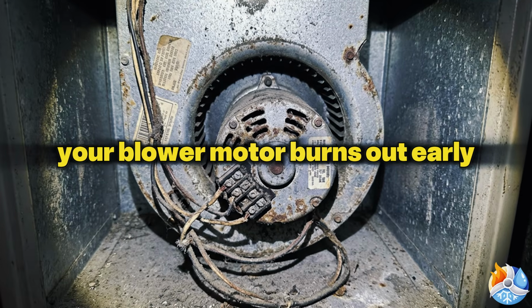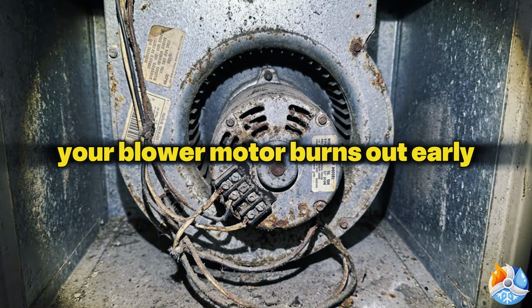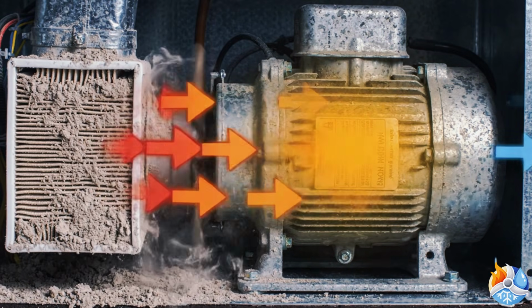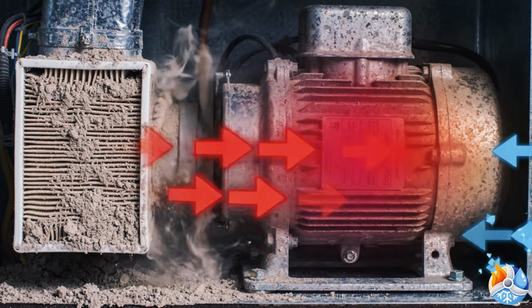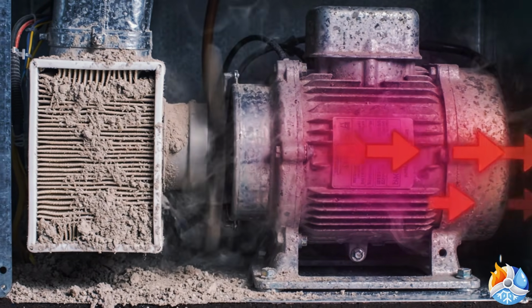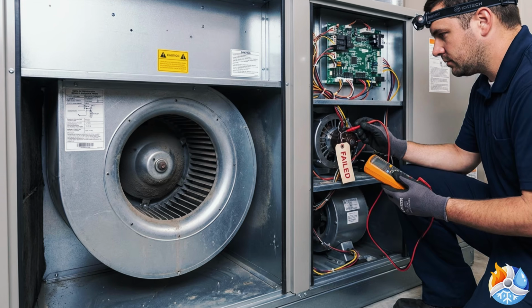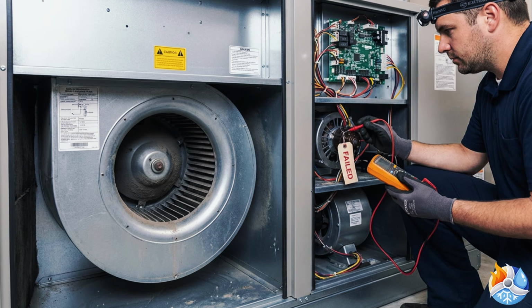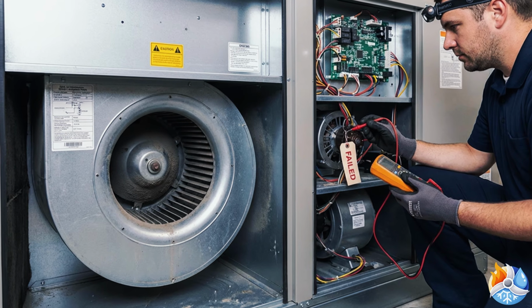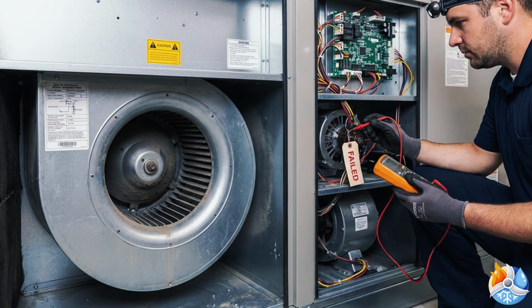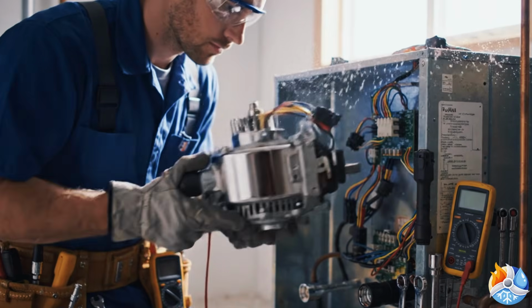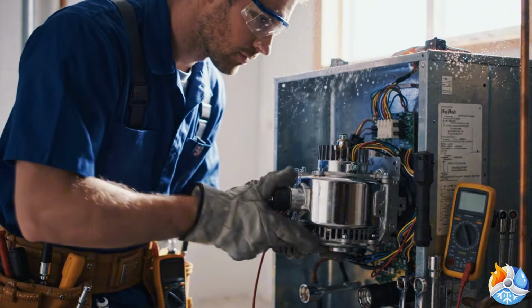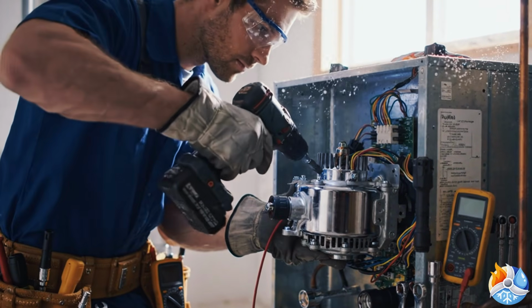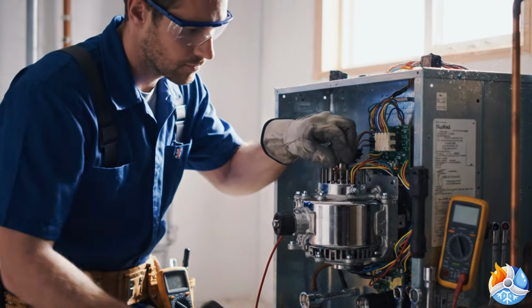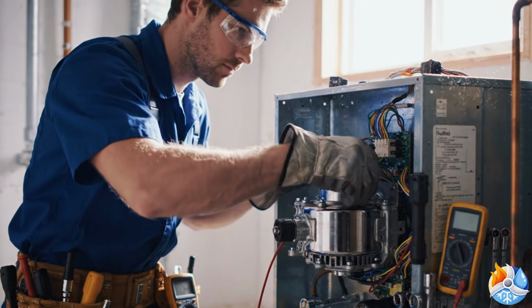Second, your blower motor burns out early. Motors that have to work against resistance run hotter. Heat degrades the motor windings over time. A blower motor that should last 15 to 20 years can fail in half that time if it has been fighting restricted airflow its whole life. Replacement, including labor, often runs $400 to $900. For high-efficiency electronically commutated motors, even more.